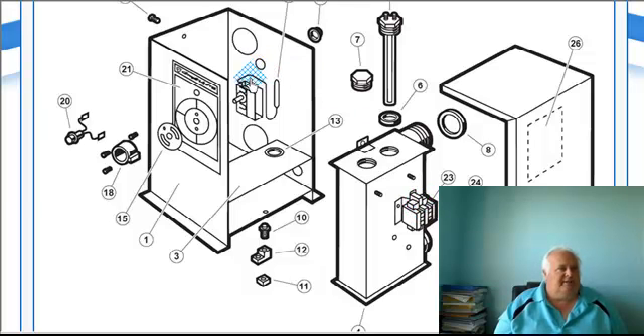Now, basically your thermostat, your pressure switch, your high limit switch is all a safety loop. All right? One continuous loop. You break the loop, you break the voltage. Now, the way I think it runs, there's a jumper wire going, I don't know if this coil is 208 or 110. You got to look on, there's the coil, okay? When this has either 110 or 220, the coil energizes, sucks that magnet in there, and gives you voltage. And then the voltage goes to the high limit, and then to your heating element. So this is a safety.